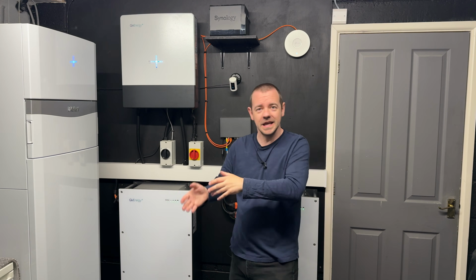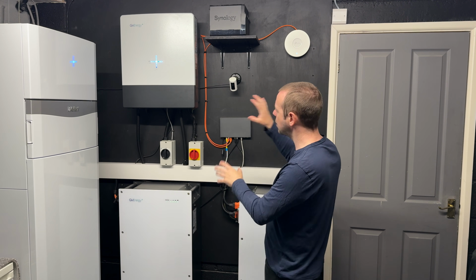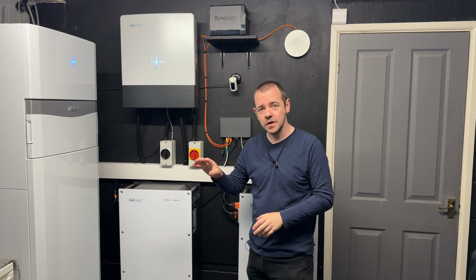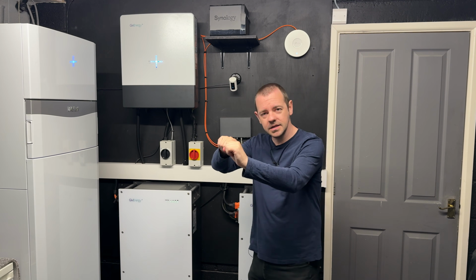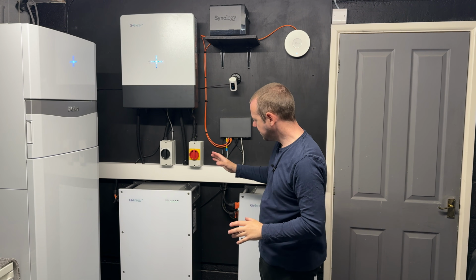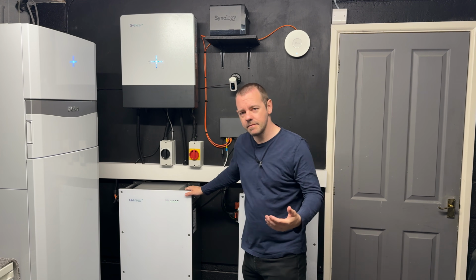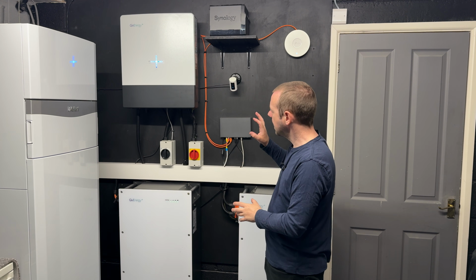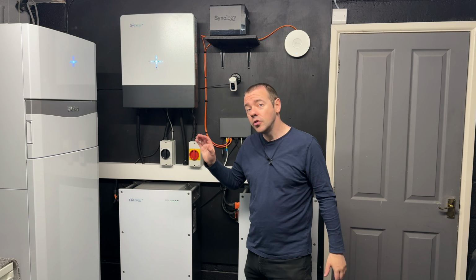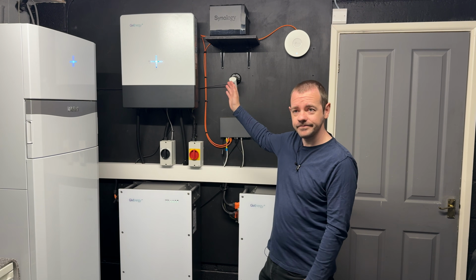So the whole "it's worked fine for ages and then it suddenly stopped" doesn't mean it wasn't a problem during installation. It could be just one of those that hasn't showed itself up yet. So I think getting them checked out every year or two is never a bad idea, just to make sure everything is tight and all the cables look okay. Yes, they're designed with no maintenance in mind, but it's never a bad thing to make sure everything is as it should be on something that costs thousands of pounds. Prevention is always cheaper than the cure.